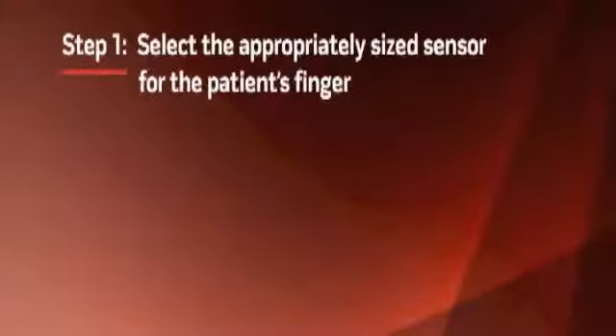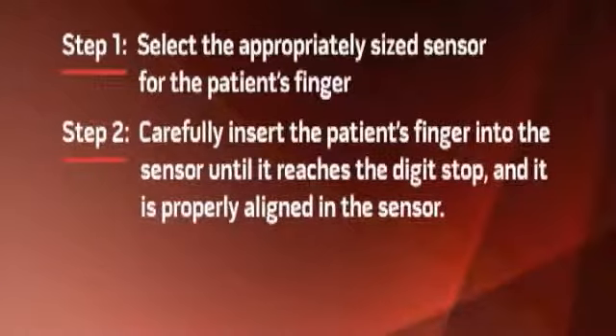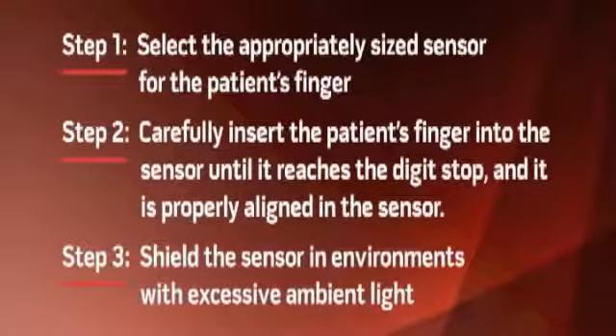So to review, proper rainbow sensor application is achieved by following these simple but extremely important steps. Step 1. Select the appropriately sized sensor for the patient's finger. Step 2. Carefully insert the patient's finger into the sensor until it reaches the digit stop, and it is properly aligned in the sensor. Step 3. Shield the sensor in environments with excessive ambient light. For more information about sensor placement and operation, consult the directions for use included with your sensor.